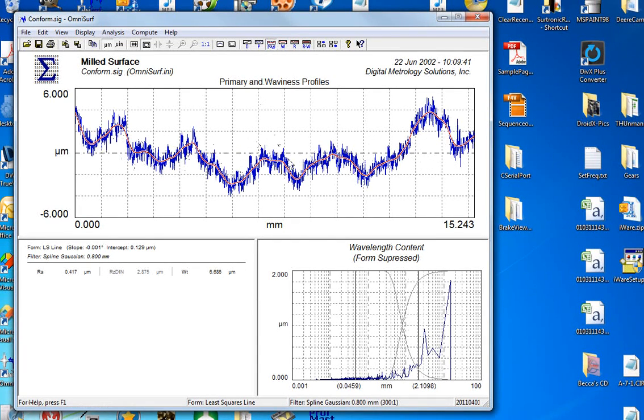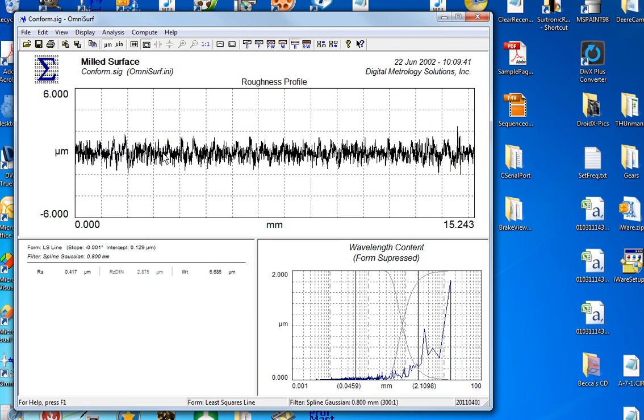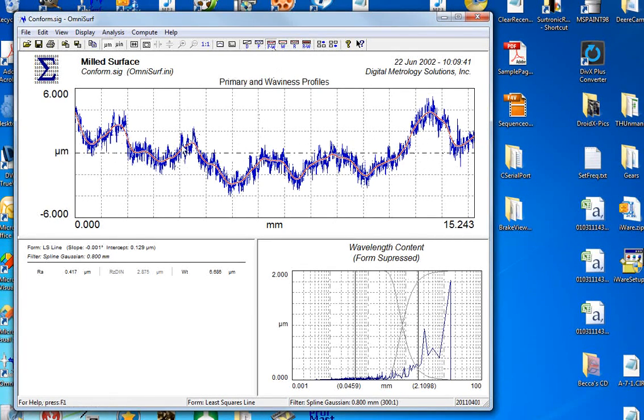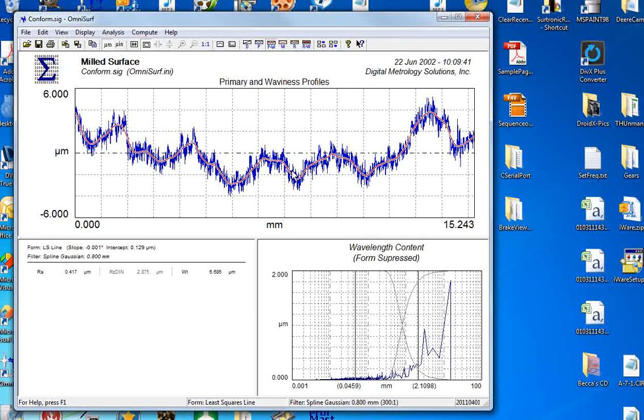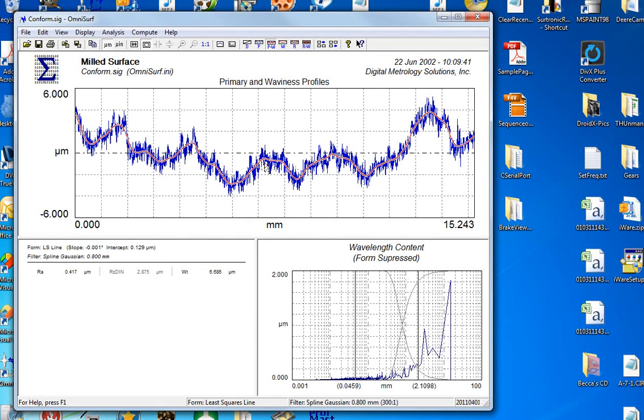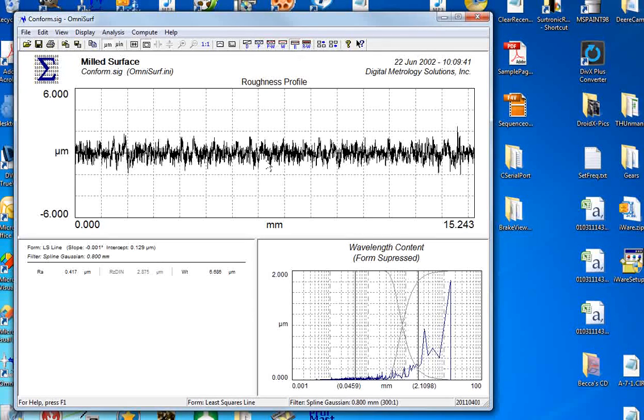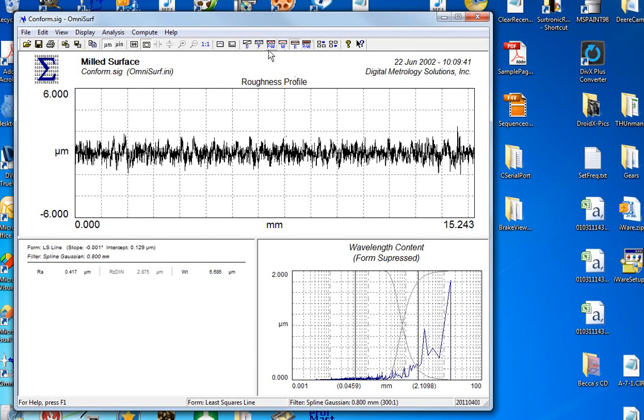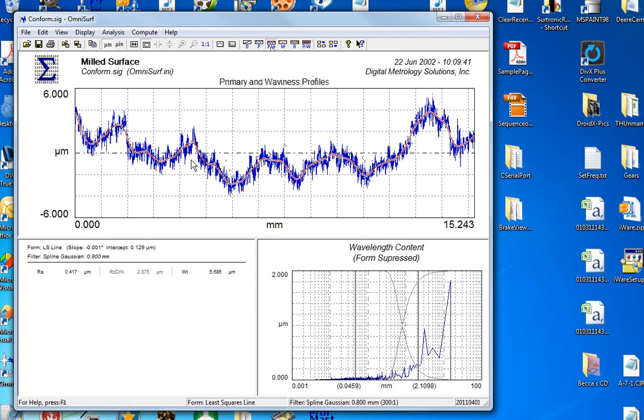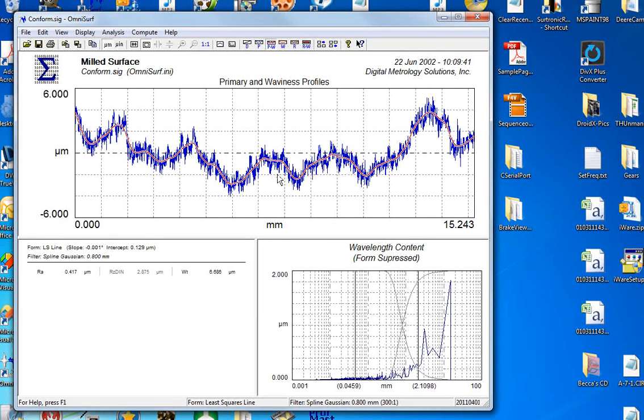There's a great deal of waviness. In fact, there's more waviness than there is roughness. The roughness profile, all of these little gray black wiggles, are exactly the same wiggles that go above and below the waviness profile on this screen. So showing primary and waviness actually also shows us roughness. With my eye, I can tell that there's roughness above and below the waviness profile right here in the middle. That is exactly the same roughness that I'm seeing right here on the roughness graph in the middle. So by showing primary and waviness we get to see the actual surface, the primary profile, we get to see the waviness, and our eye can interpret the roughness profile.